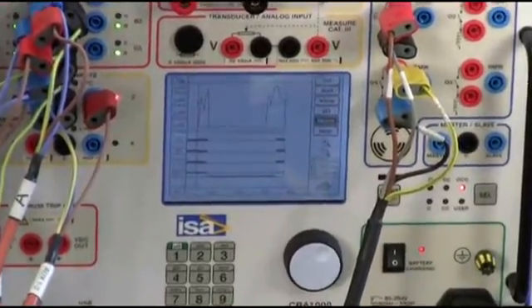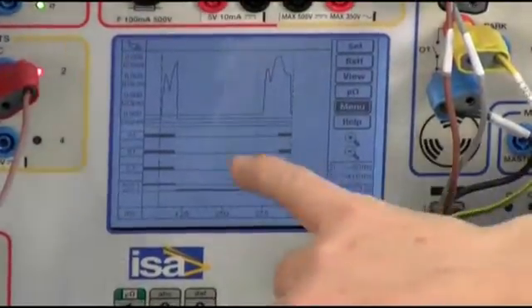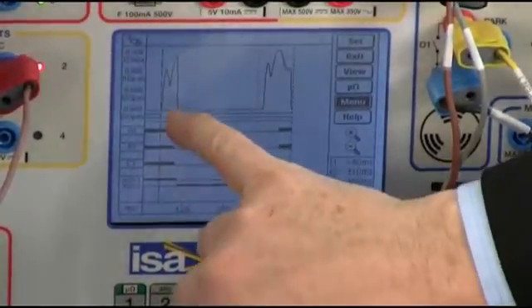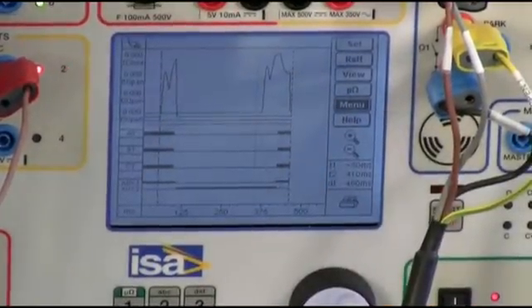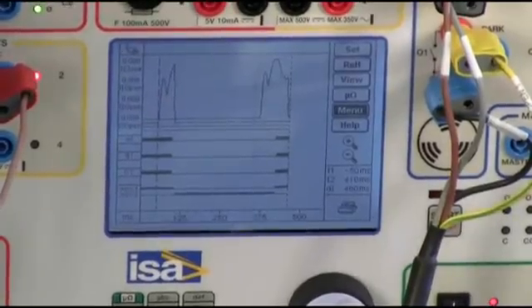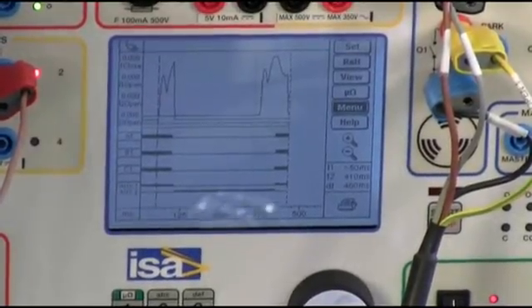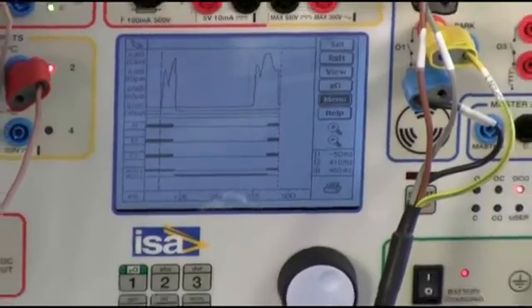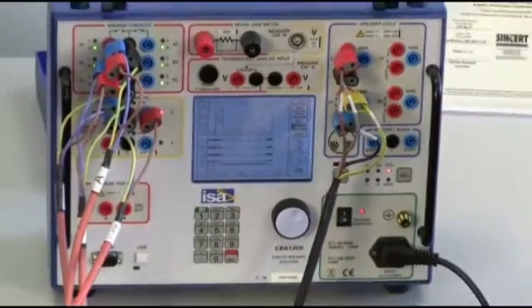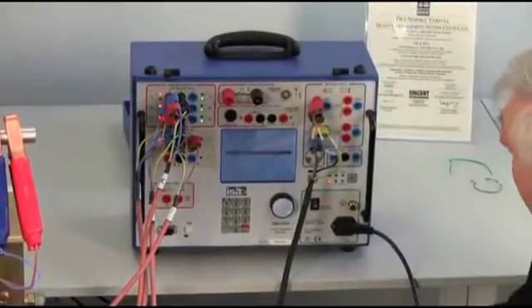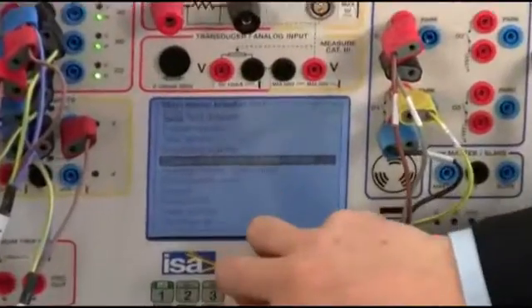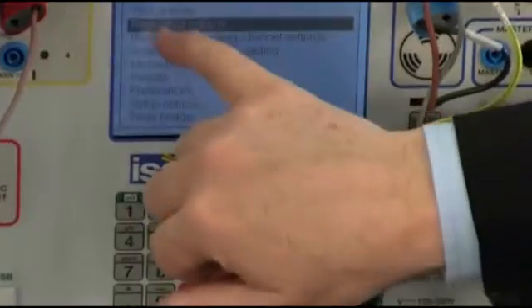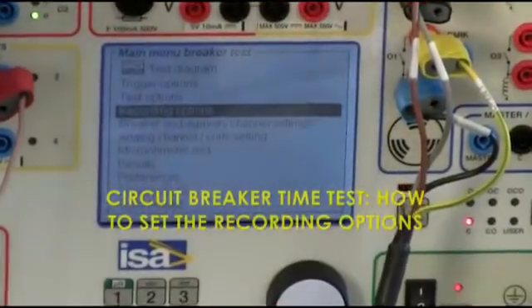And here we are. What do we have here? Here is the open coil current, the closed coil current, but I don't see the next open coil current. Why? Because I forgot changing the test recording to duration. Once I have set the breaker auxiliary contacts, there is another thing that I have to do, that is set the recording option.